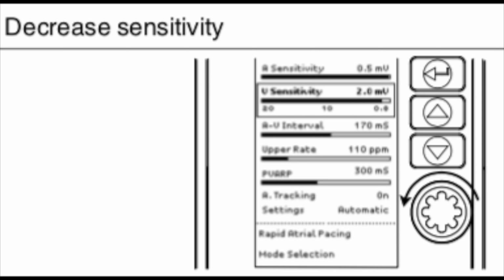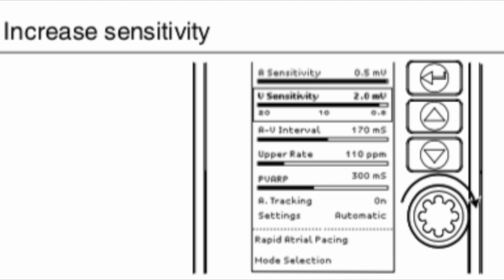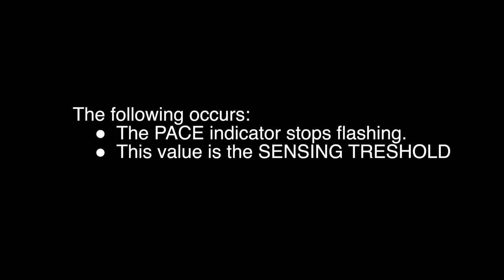6. Navigate to the sensitivity settings. 7. Decrease sensitivity. Slowly turn the menu parameter dial counterclockwise. Increase mV value until the sense indicator stops flashing. The pace indicator flashes continuously, but capture is not likely because the output value is set to minimum. 8. Increase sensitivity. Slowly turn the menu parameter dial clockwise. Decrease mV value until the sense indicator starts flashing. The following occurs. The pace indicator stops flashing. This value is the sensing threshold.